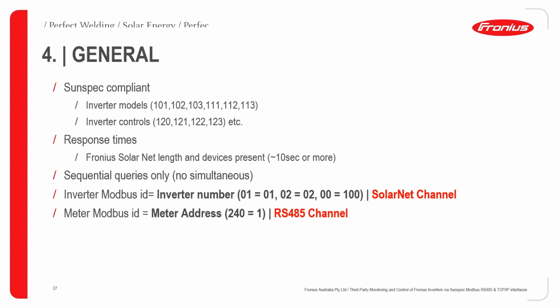Going forward, in terms of SunSpec compliance, we've implemented the models shown there, as well as the controls. I'll share the information below as we go, but you can delve inside the registers and see the representative values they bring. A key note to think about: response times. When you submit a request, how long will it take for the actual device to respond? It depends on the length, and depends on the devices. Obviously, that's a variable; it can be up to 10 seconds, 5 to 10 seconds, possibly even more. Something to think about while you do the integration.